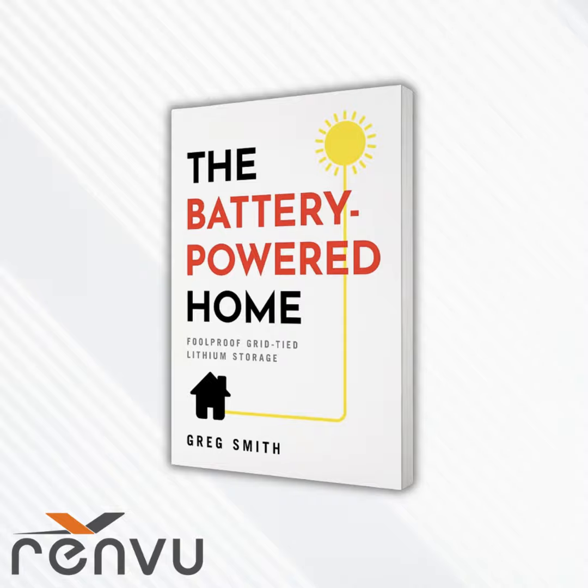That's what a lot of people do. However, what I tell people is that you should play around with these settings. Most battery systems have 2 or maybe 3 timers you can set. If your peak window is done at 9 o'clock and you still have 40% state of charge, just open that window up a little bit more - save some more money. It doesn't matter, you're not going to hurt anything. You can open the window up on the front end or the back end and go more into the night. It's only going to benefit you.